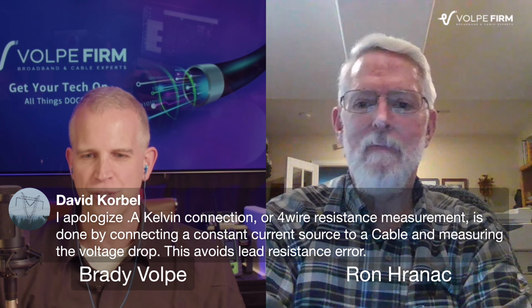David says: a Kelvin connector, or 4-wire resistance measurement, is done by connecting a constant current source to a cable and measuring the voltage drop. This avoids lead resistance error. So that's the Kelvin measurement, and it wouldn't surprise me if the lab grade equipment at the factory is something like this. By the way, when using the word Kelvin, other than to describe Lord Kelvin, it's always lowercase - the abbreviation is an uppercase K, but when talking about kelvin as in thermodynamic temperature, it's lowercase.